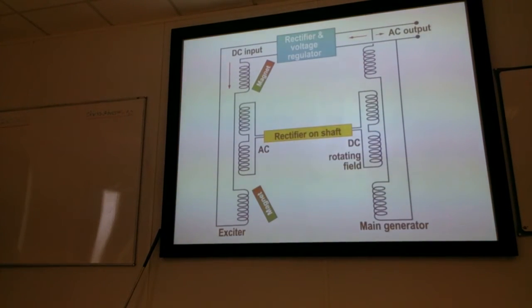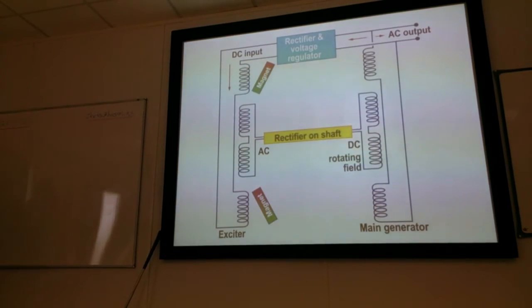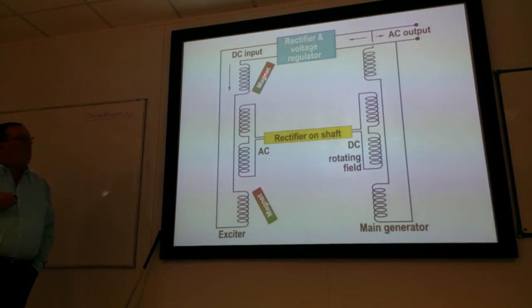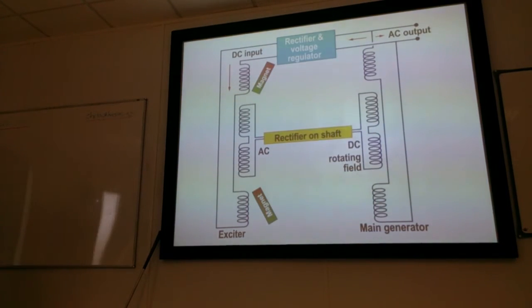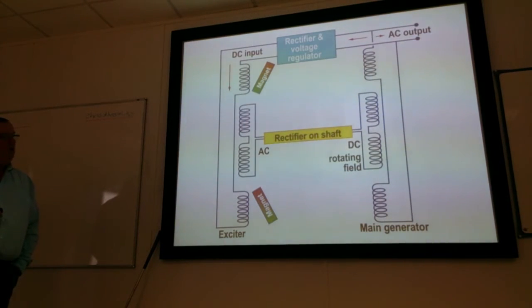This is a typical brushless self-excited AC generator. Now what we've got is a pair of small permanent magnets in there, which is what's going to give us some residual magnetism for the initial excitation current. Once we've got that going, the DC on the other end of the shaft will produce the current that we require for the main field windings. This is a sketch diagram of what you saw on the animation there, where you've got AC on one end of the shaft and a small DC generator on the other end of the shaft. So a self-excited system.